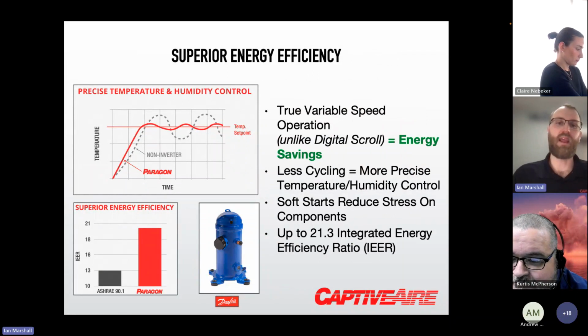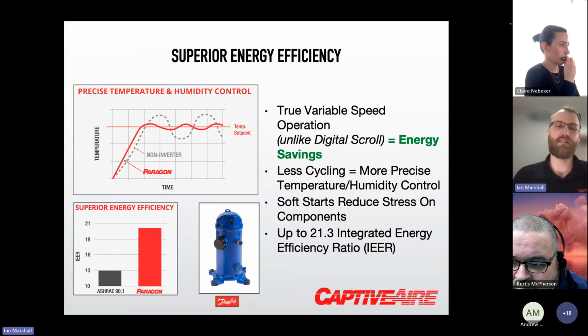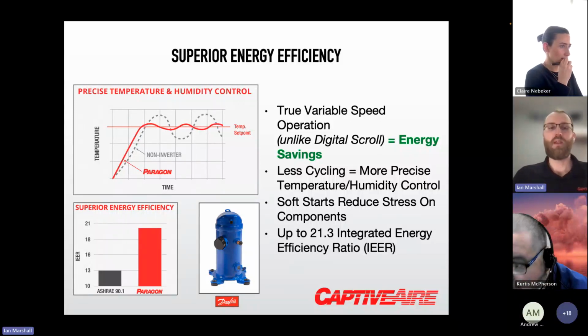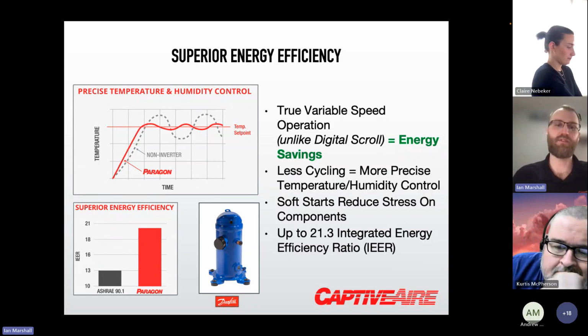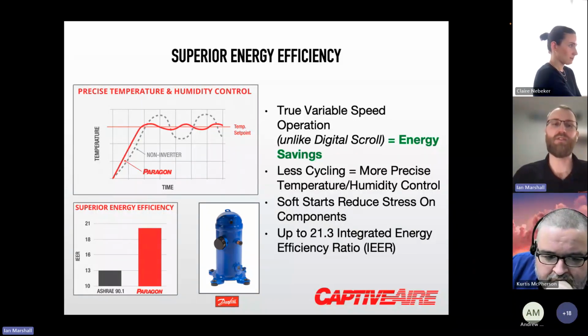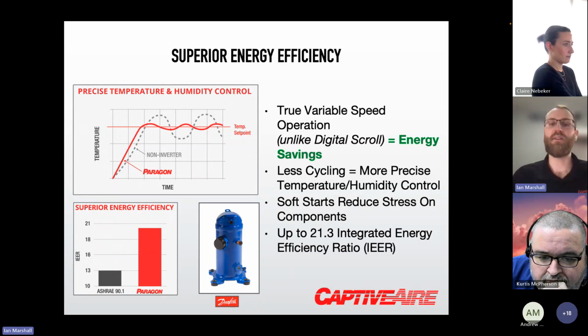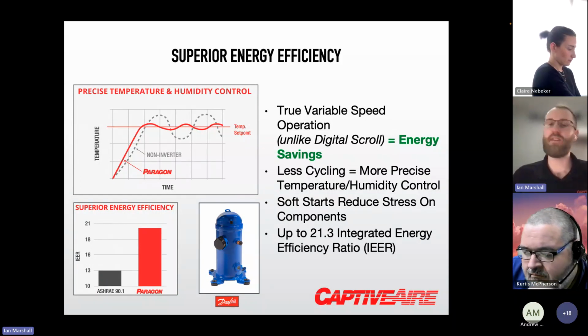So with that, we get quite a bit of energy savings on the cooling compressor side, because again, that compressor is tied to a VFD. So when we're looking at controlling to a space temperature, we're able to control to that temperature in a much more precise manner because of the variable speed compressor. And with that, you get the energy savings because you're actually slowing the speed of the compressor down.